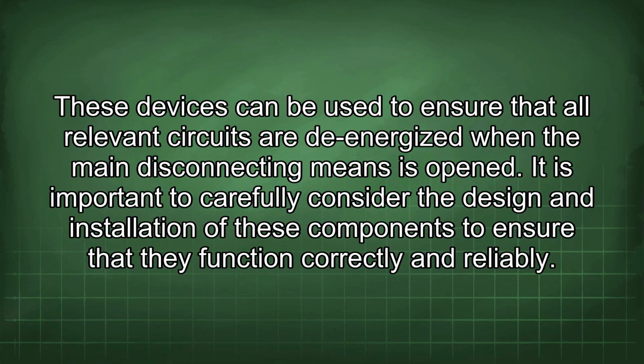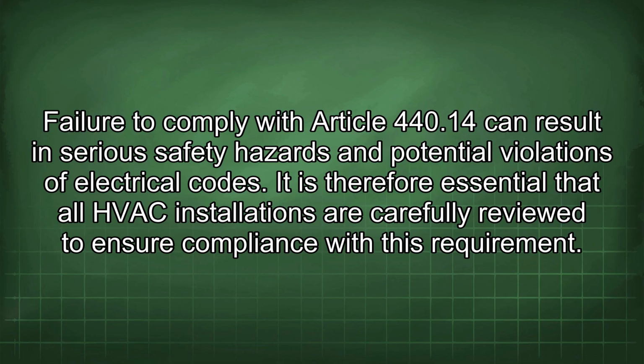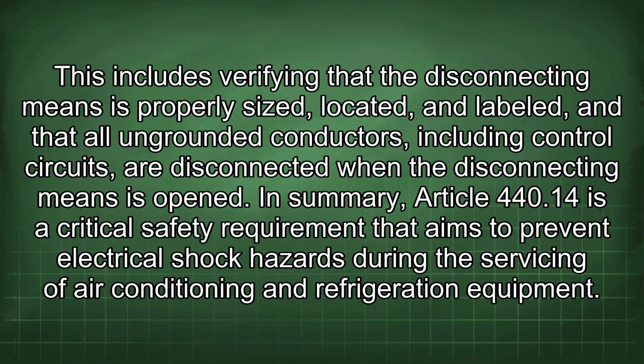It is important to carefully consider the design and installation of these components to ensure that they function correctly and reliably. Failure to comply with Article 440.14 can result in serious safety hazards and potential violations of electrical codes. It is therefore essential that all HVAC installations are carefully reviewed to ensure compliance with this requirement. This includes verifying that the disconnecting means is properly sized, located, and labeled, and that all ungrounded conductors, including control circuits, are disconnected when the disconnecting means is open.